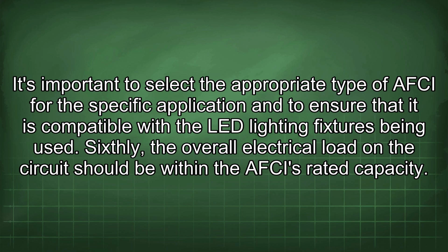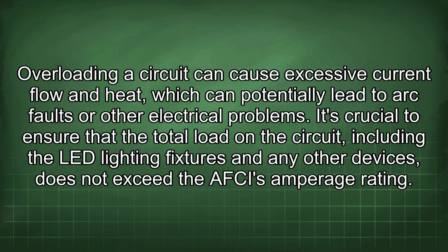Sixthly, the overall electrical load in the circuit should be within the AFCI's rated capacity. Overloading a circuit can cause excessive current flow and heat, which can potentially lead to arc faults or other electrical problems. It's crucial to ensure that the total load on the circuit, including the LED lighting fixtures and any other devices, does not exceed the AFCI's amperage rating.